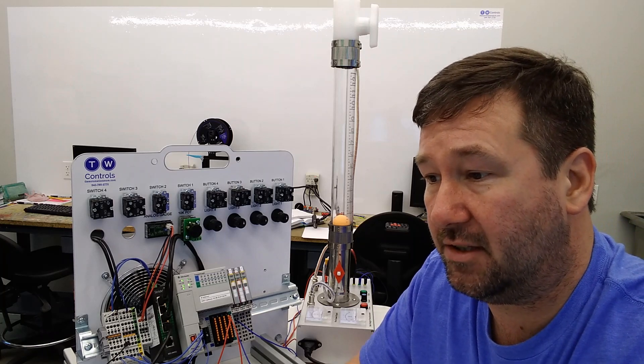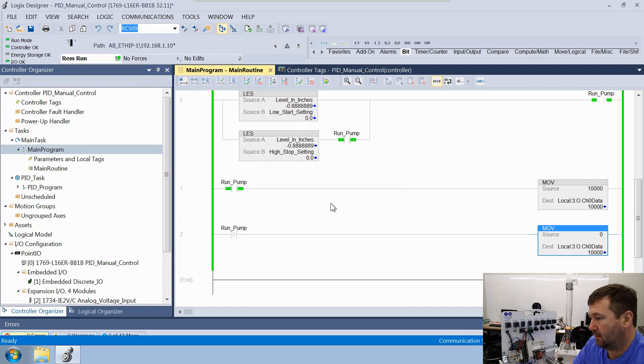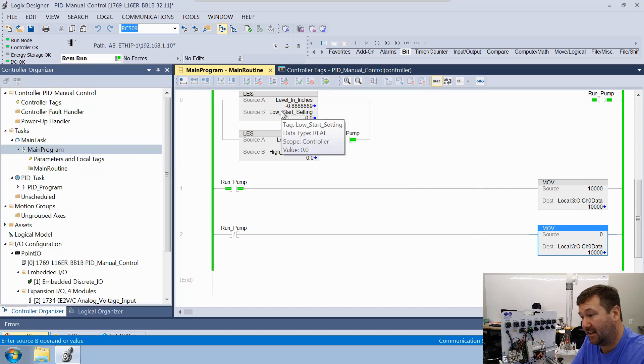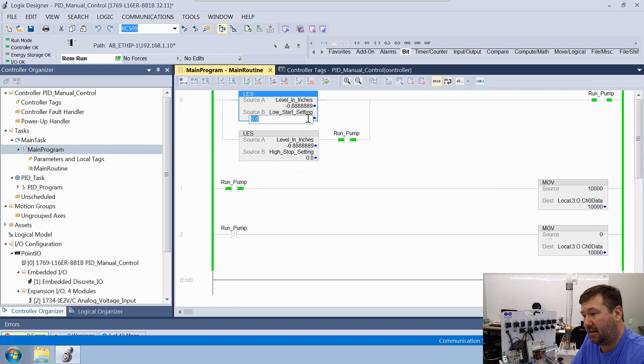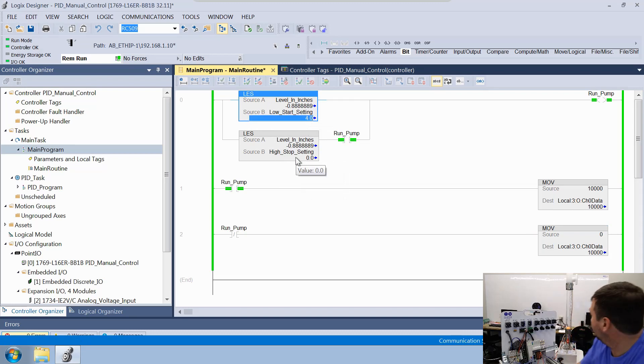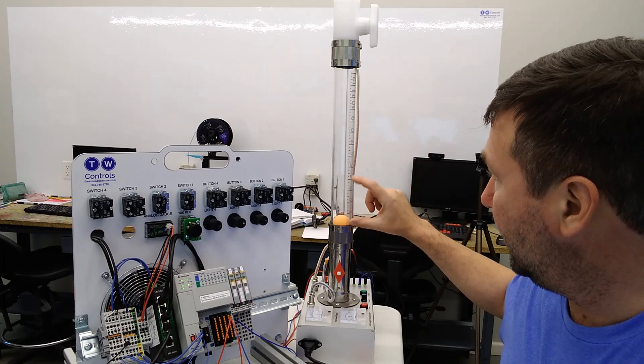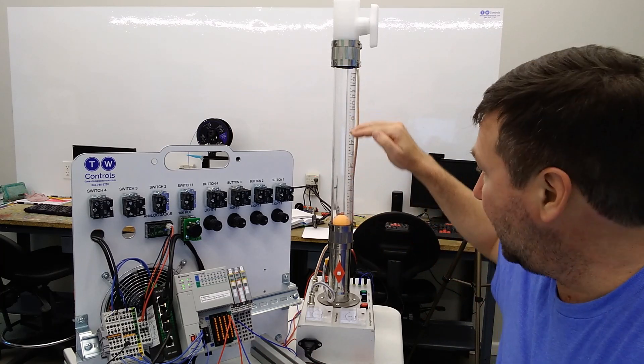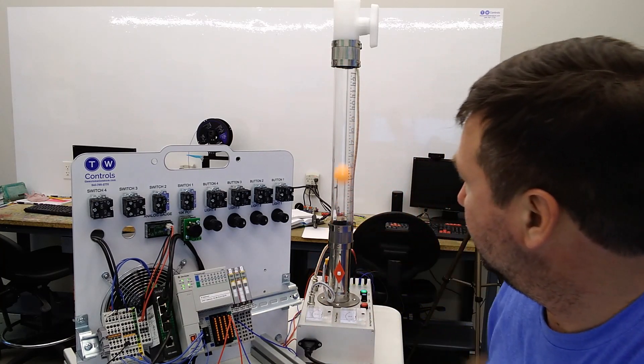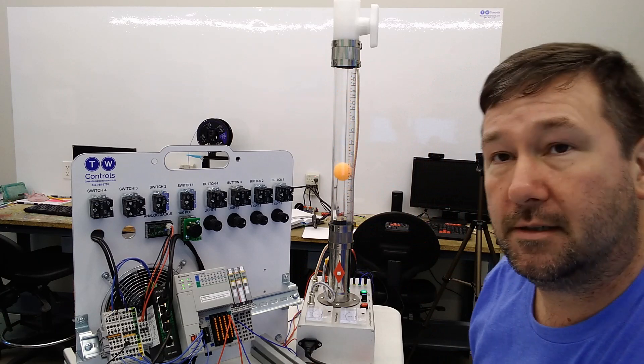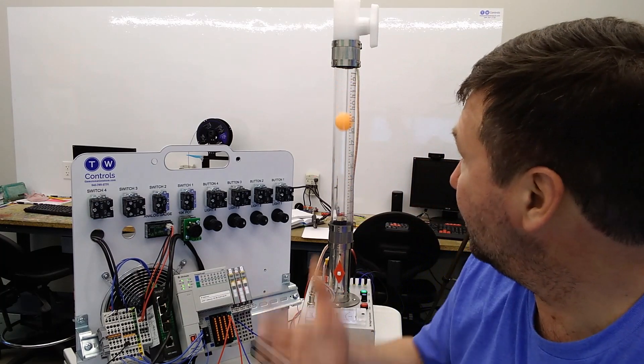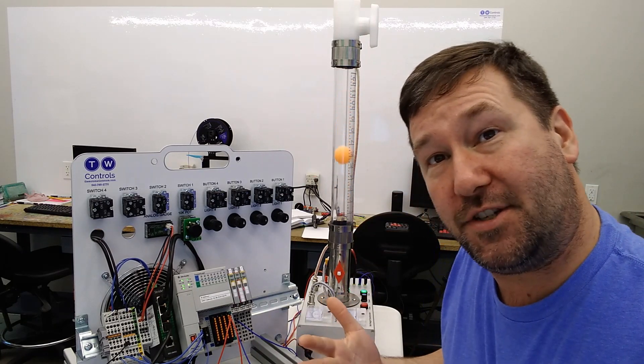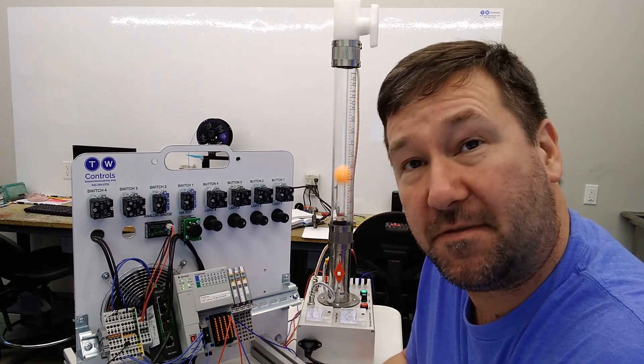Let's try this out. I'm going to download this program and then we'll switch to run mode. It's saying 10,000. Let's turn this back on now. Actually, we need to put some values in this low start setting and high stop setting. We can just double click right here. Our low, I want to start that at four inches. Then we want to stop it at eight inches. So what this should do is it should make the pump kick on if we're below four. As soon as we get up to eight, it should stop. It should stay between four and eight. Let's see how it works. I'm going to turn this on. This is very basic on and off control. You can see we're overshooting on the top end. We're actually going down too low, so a lot of issues. But for a lot of applications, this works just fine.